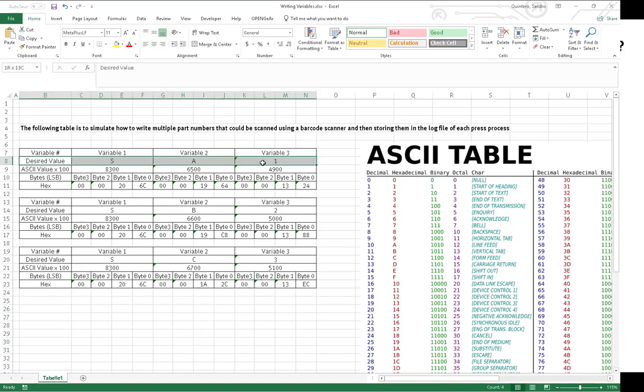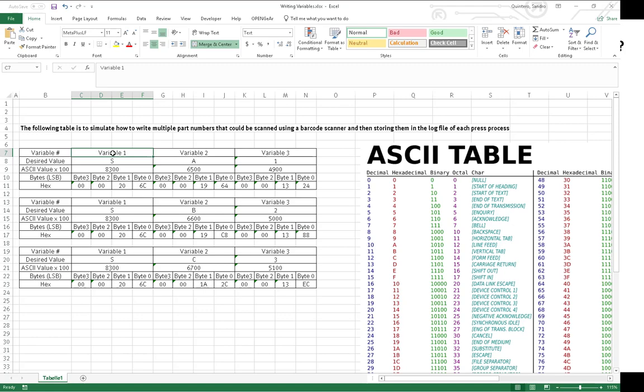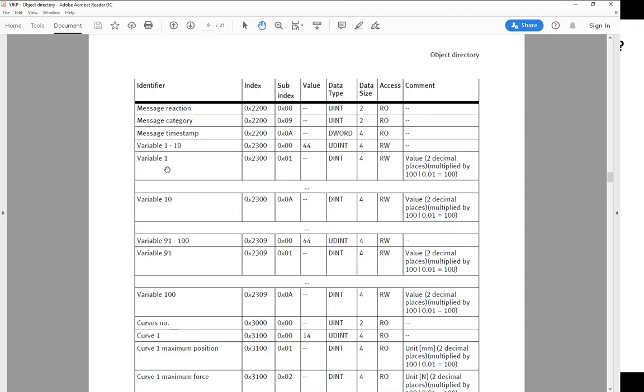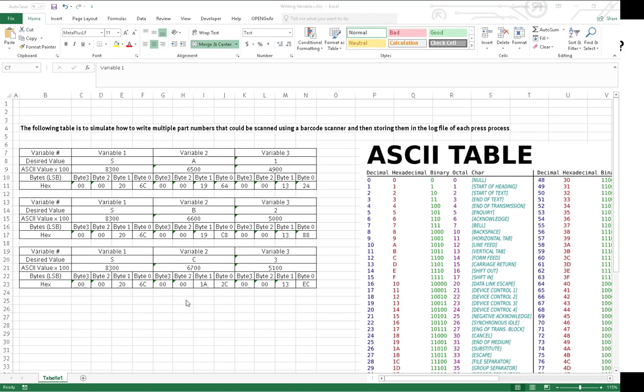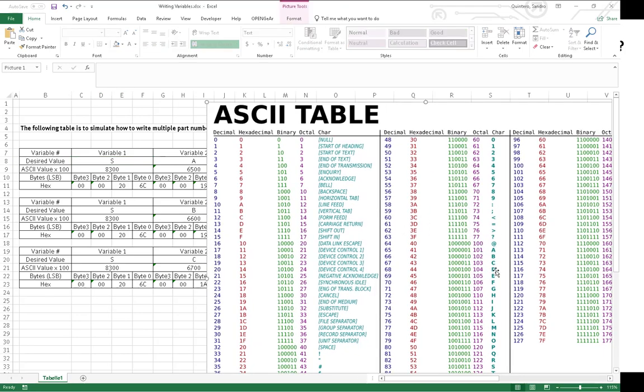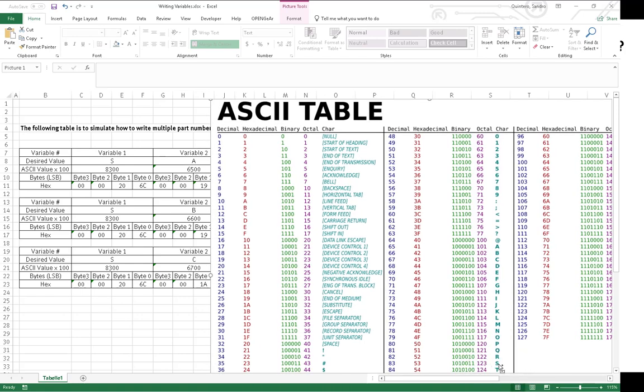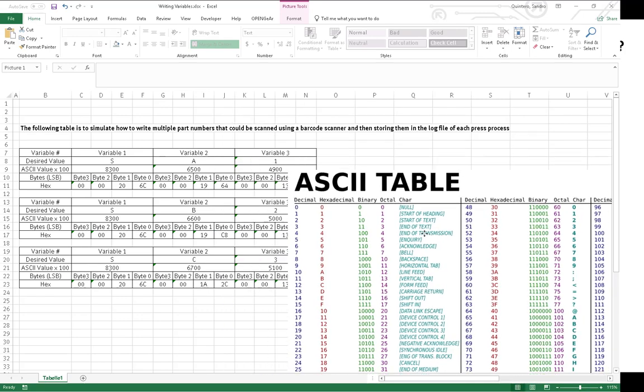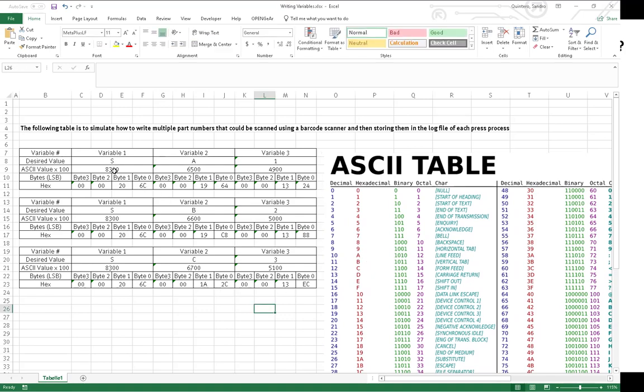For the first one, SA1, I'm going to be using three variables, one for each character. Since the variables are represented in the servo press as floating point reals, and the manual says they are multiplied by 100, you'll see a resolution of 0.01. If I go to my ASCII table and want to set an 'S', the decimal value for S is 83. The way the variables work is by multiplying by 100, so that gives me 8,300. It's the same for A and 1 in this first pass.